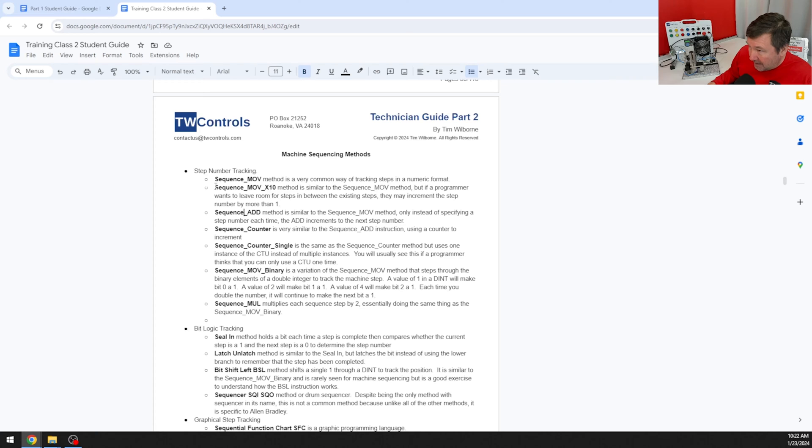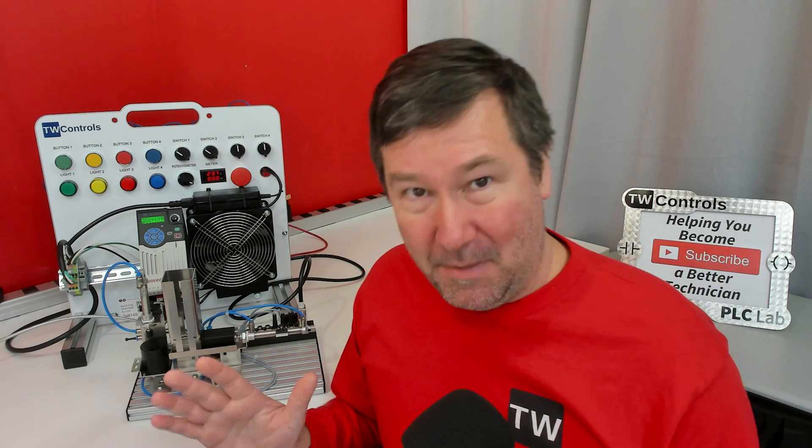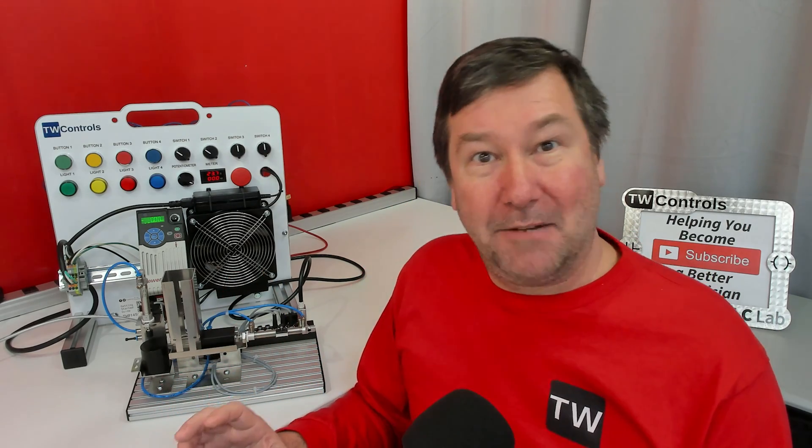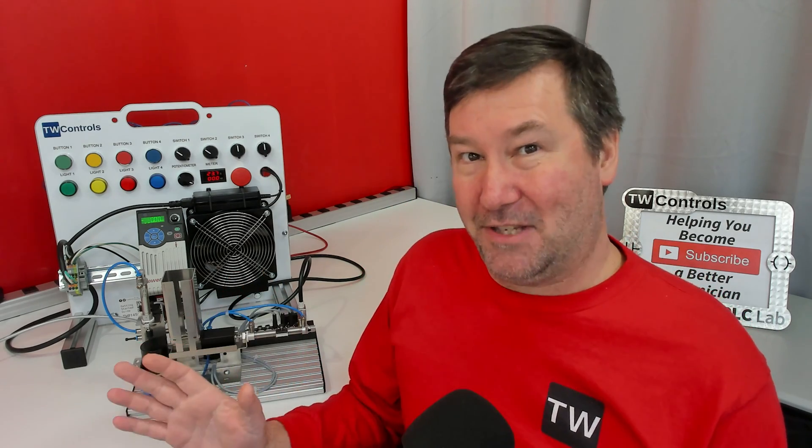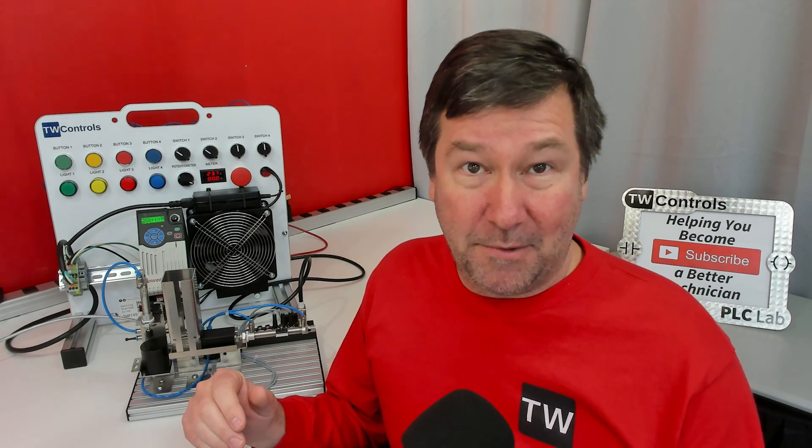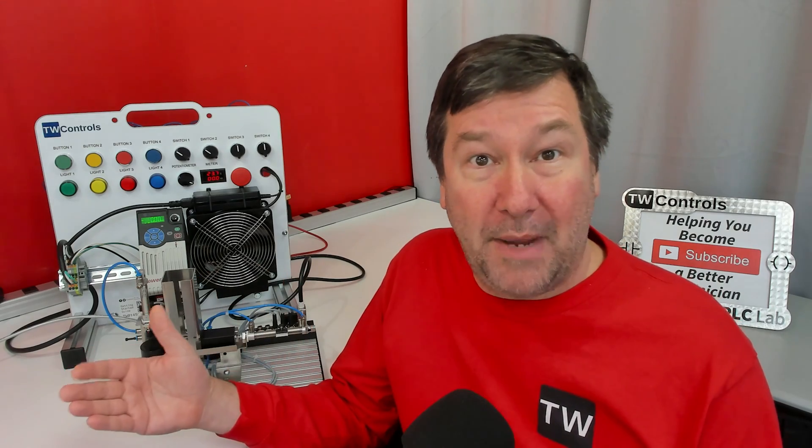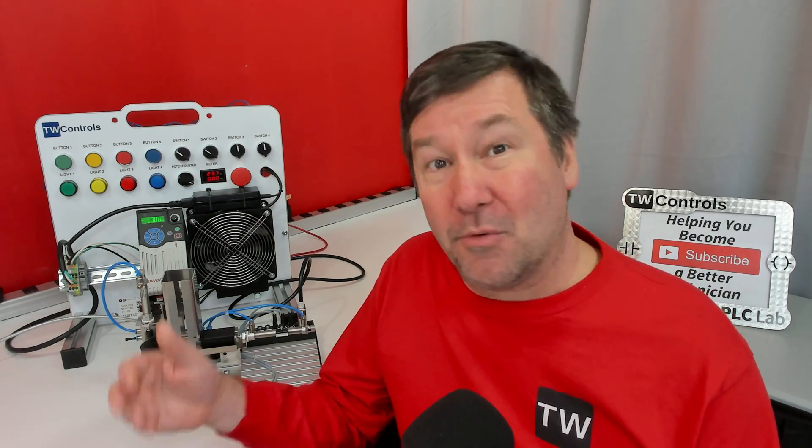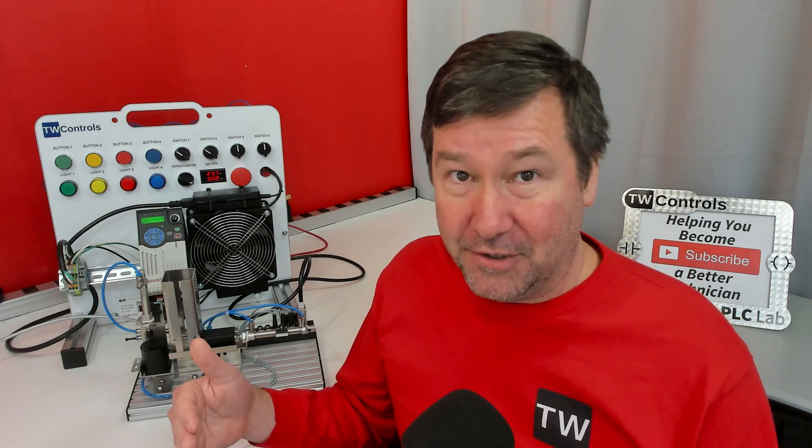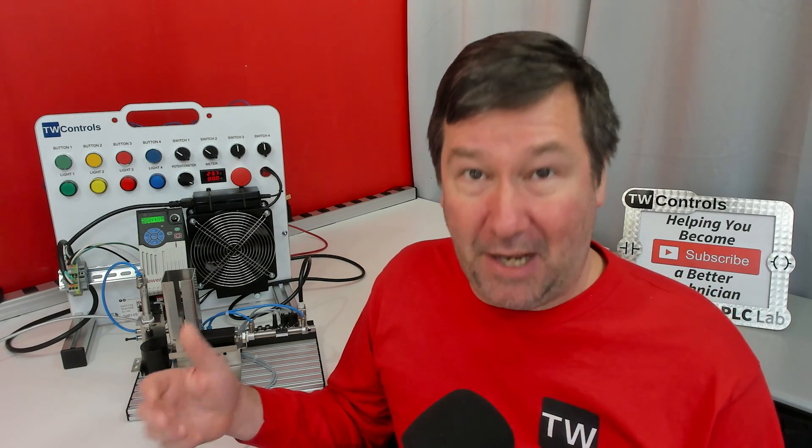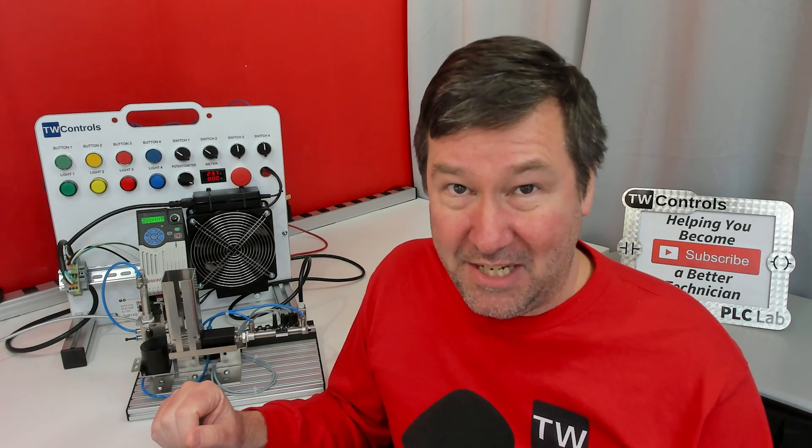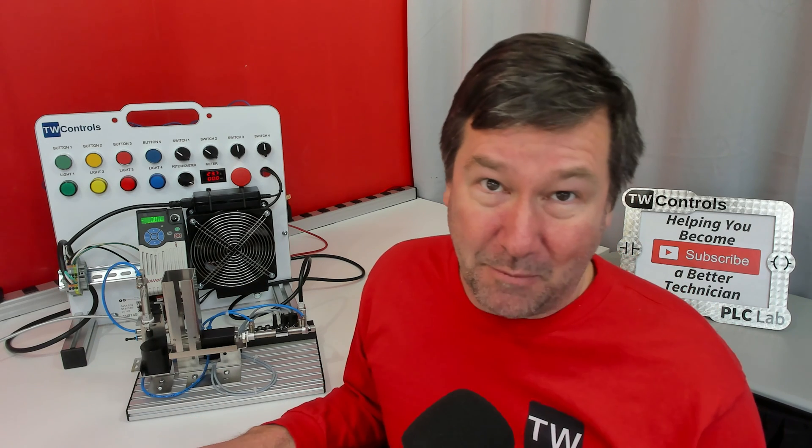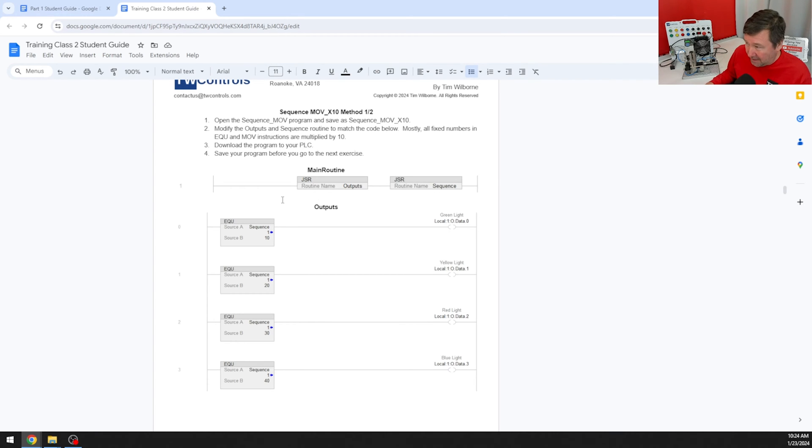In this video, we're going to talk through how a little bit of planning up front will make our programming life a whole lot easier. For my programming, I'm going to use the sequence move times 10 method. This is not the most sophisticated method, but it leaves you a lot of opportunity for additions when you forget a step or when you're making upgrades later on. It's also really easy for someone to come behind you, look at your programming code and troubleshoot it.